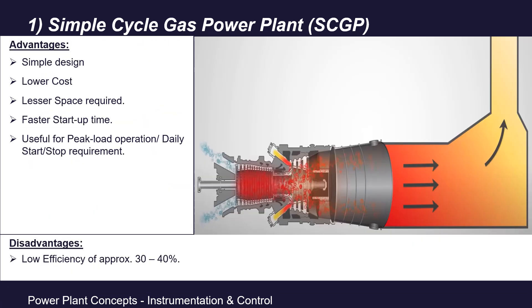The simple cycle gas power plant is very simple in design and has a lower cost compared to closed cycle and combined cycle power plants. As the number of components is very less, it requires very less space. The main advantage is its faster startup time to reach full capacity. Due to this faster startup time, it is very useful to cater to peak load requirements, generally in power plants where daily start and stop is required.